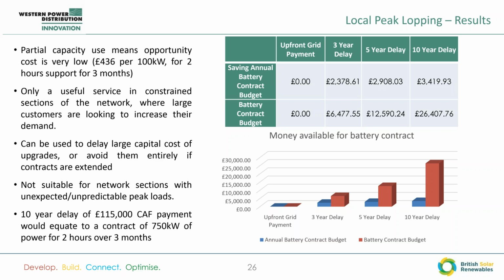It doesn't work out well for network sections with unexpected and unpredictable loads, because then you have to contract for a longer time and the opportunity cost goes up. But this use case isn't always about absolute cost versus the cost of reinforcement. Sometimes there's quite a large delay on when DNOs are able to schedule the reinforcement, and waiting 2 to 3 years for a connection to be upgraded could be damaging for a business falling behind its rivals.